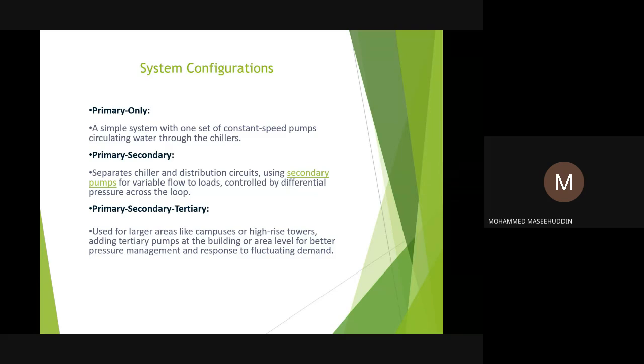Okay, now when it comes to system configurations, what do we mean by system configuration? In any chilled water system, there ought to be different circuits, because if it's a high-rise building like a big tower, we cannot have a single circuit of chilled water pumps. So basically we start with primary pumps, as I told you in one of my earlier slides as well. The purpose of the primary pumps is to pump the water from the source to the chillers, and they run at constant speed, because it is not varying with varying loads. It is just to transfer the water.